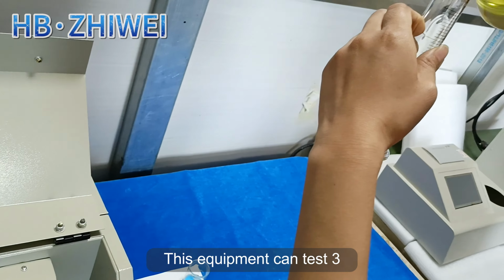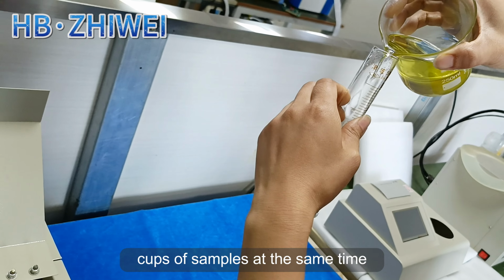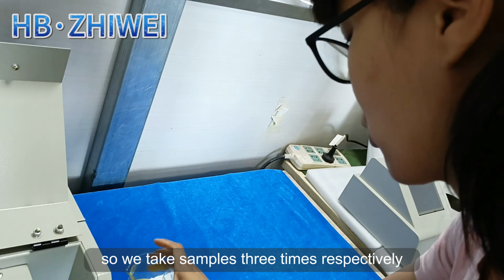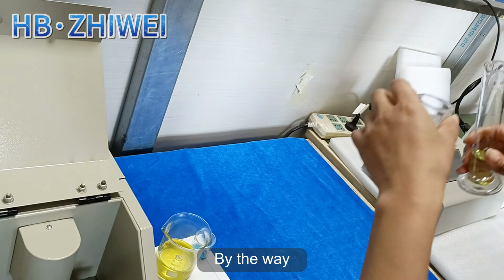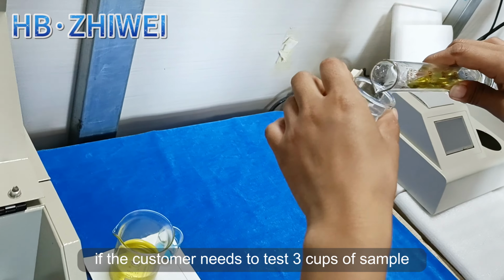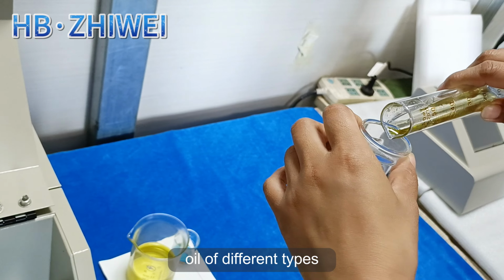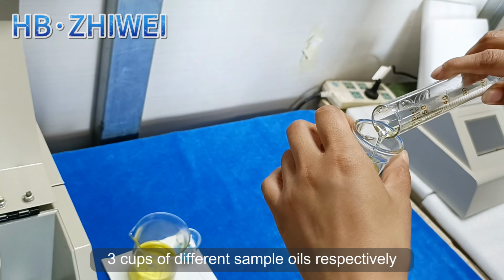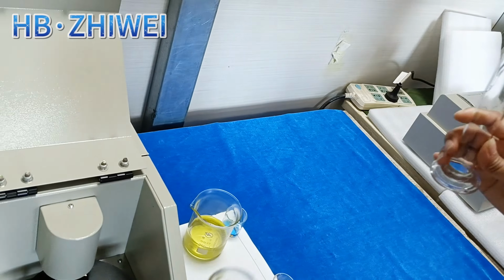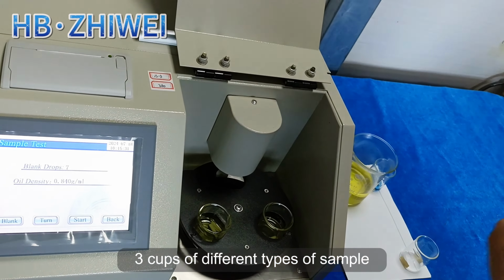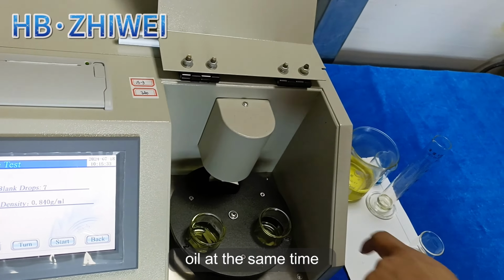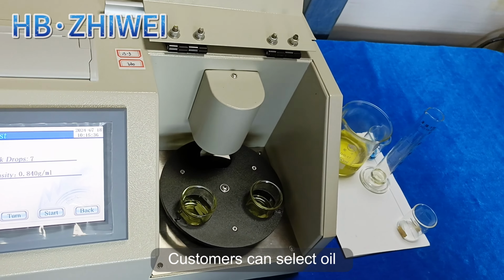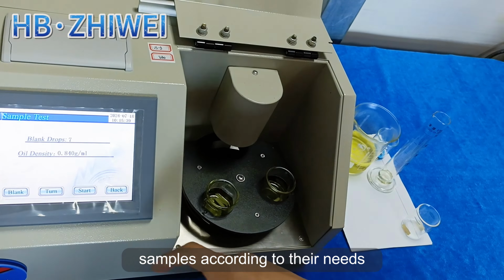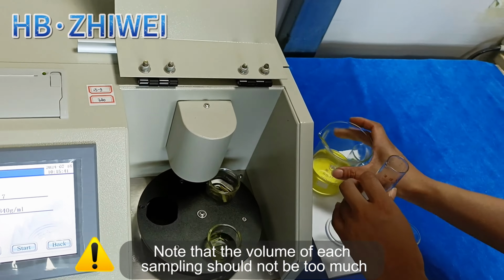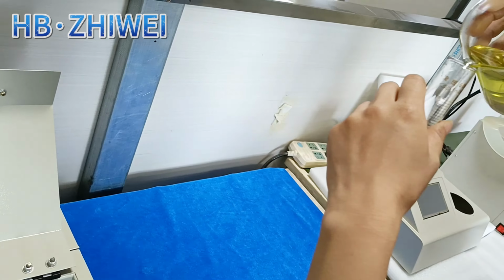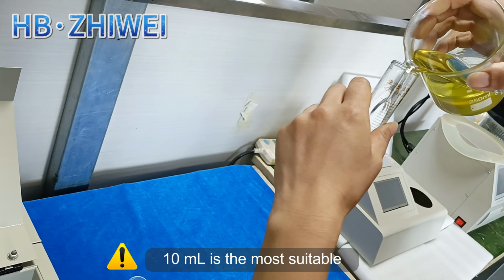This equipment can test 3 cups of samples at the same time, so we take samples 3 times respectively. By the way, if the customer needs to test 3 cups of sample oil of different types, they can also select 3 cups of different sample oils respectively. This equipment can test 3 cups of different types of sample oil at the same time. Customers can select oil samples according to their needs. Note that the volume of each sampling should not be too much. 10 ml is the most suitable.